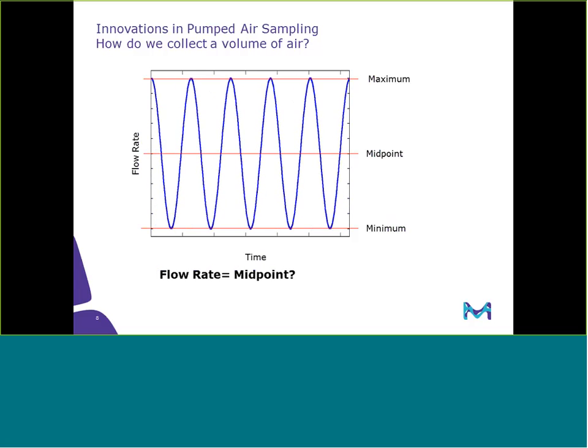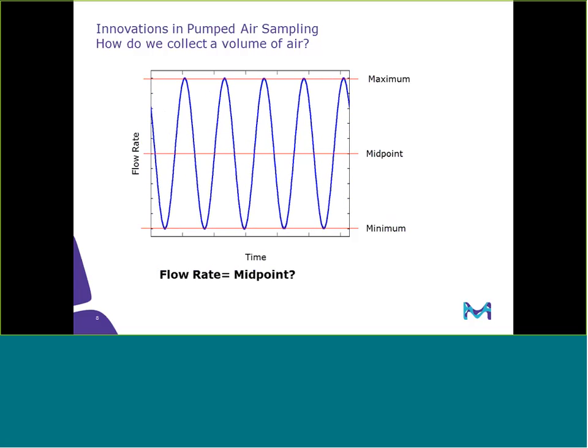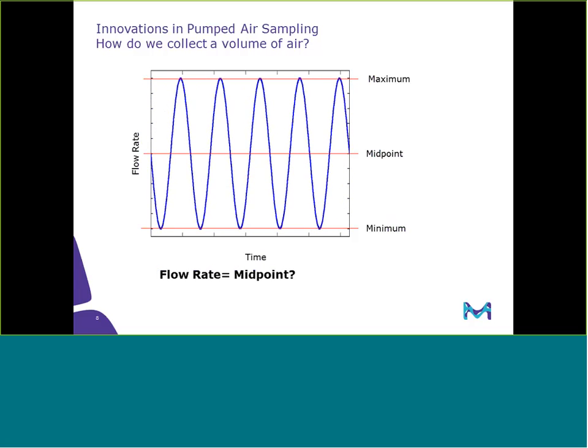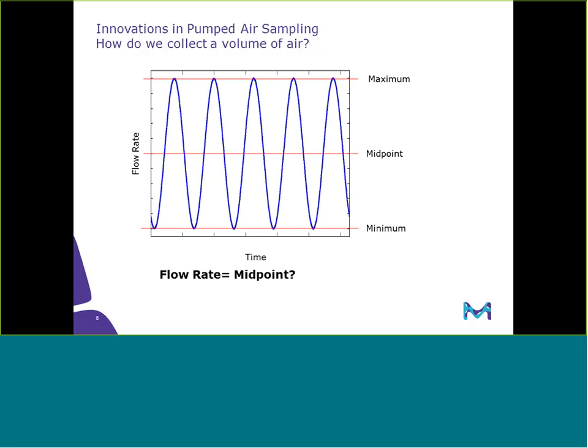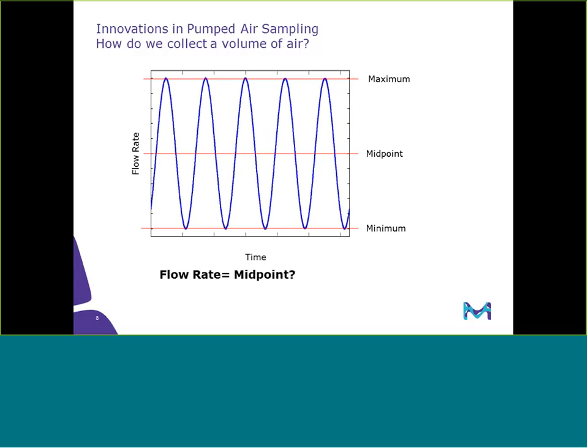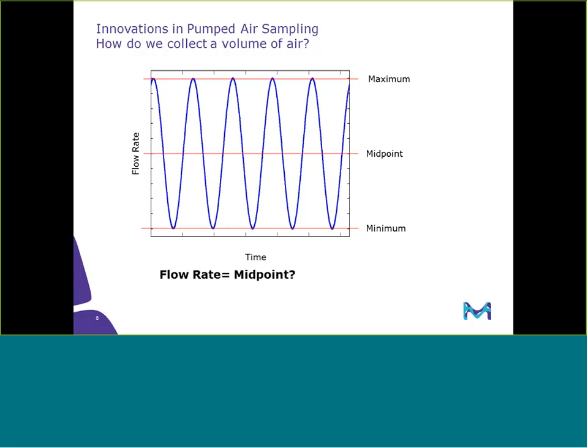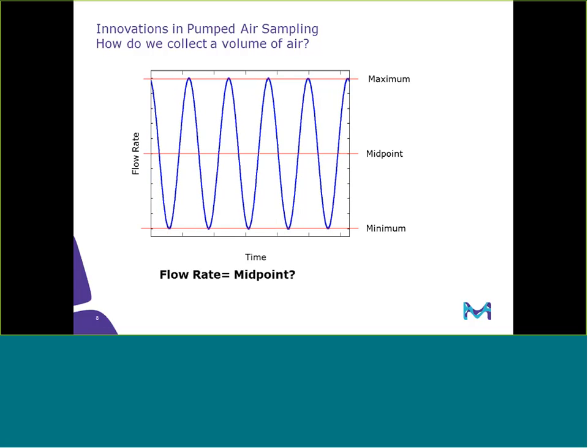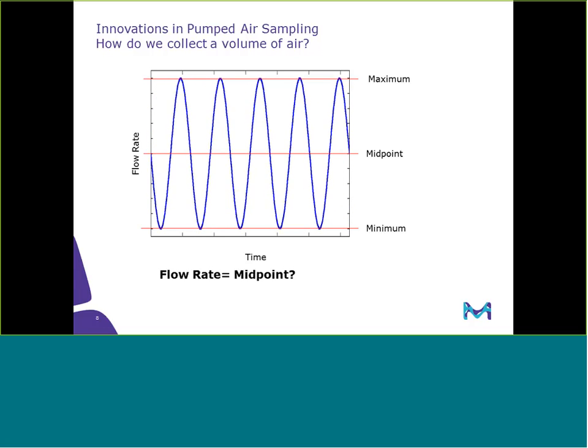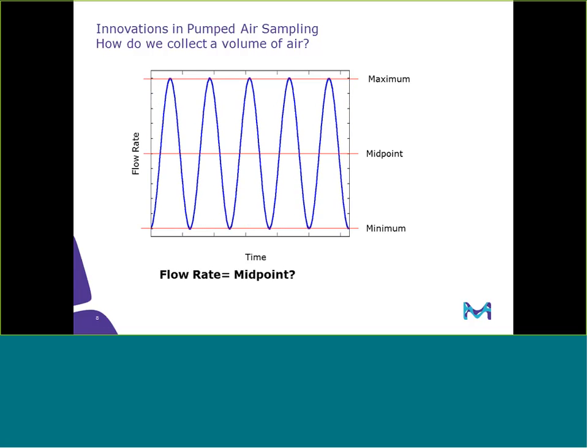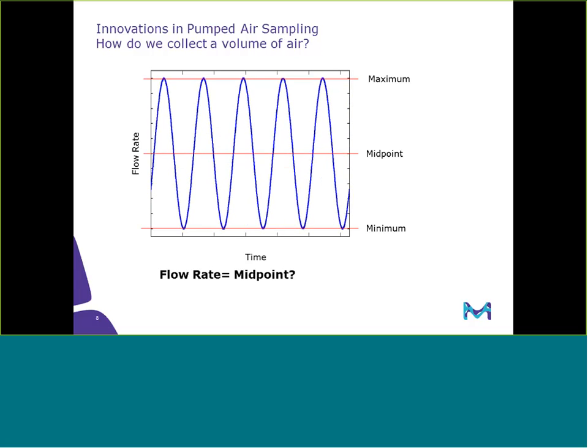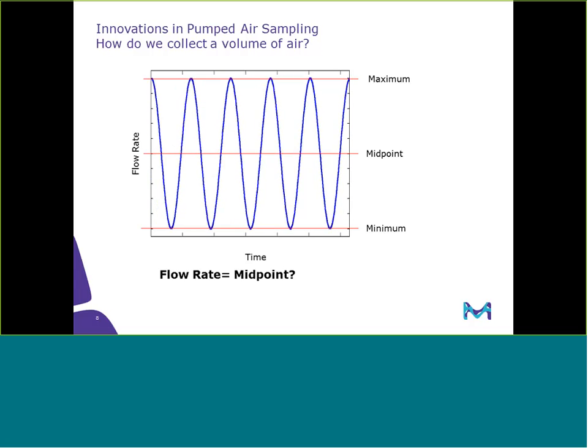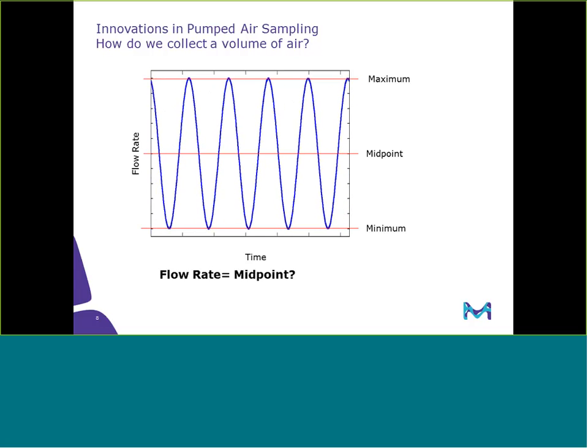Well, the problem often with this calculation is that the total volume of air is a measurement based on an average midpoint value in this ideal waveform, and not a true and accurate integrated measurement, which would involve integration of the exact waveform function in a dynamic environment. Hence the need for a calibration device.